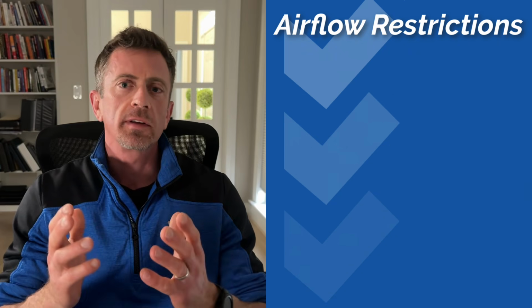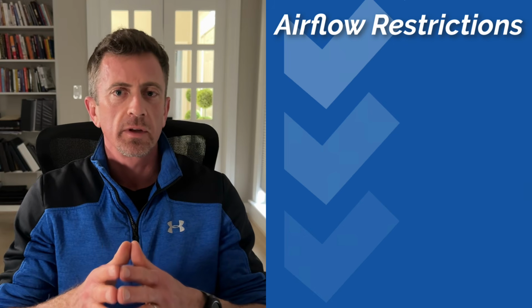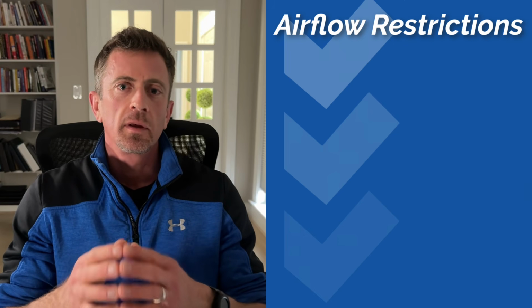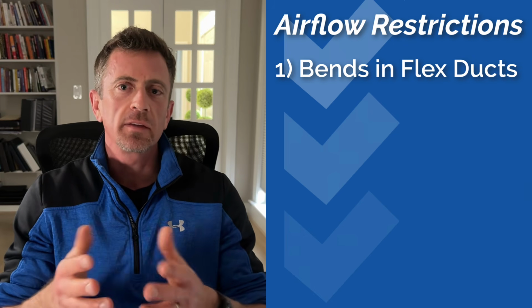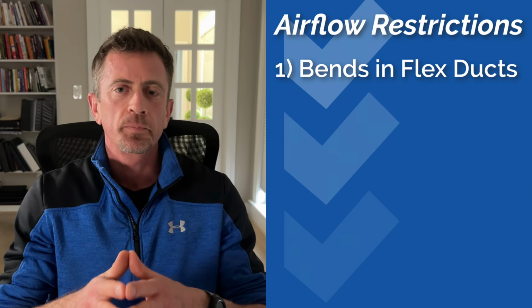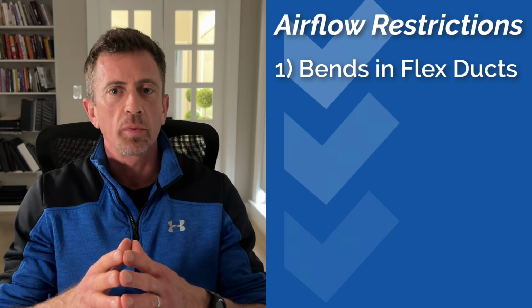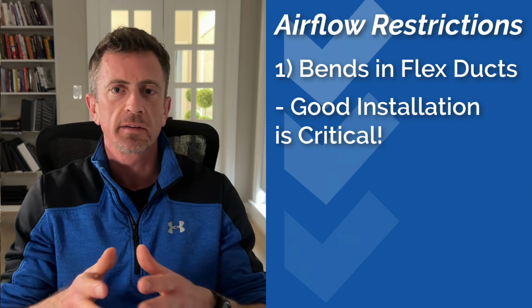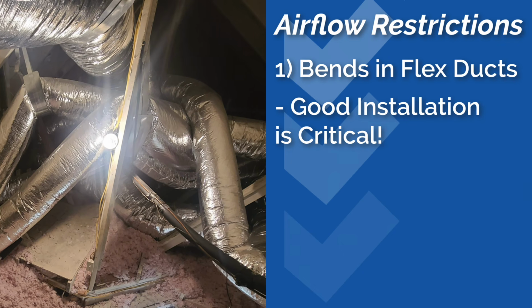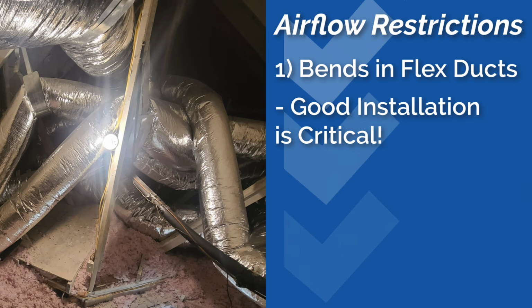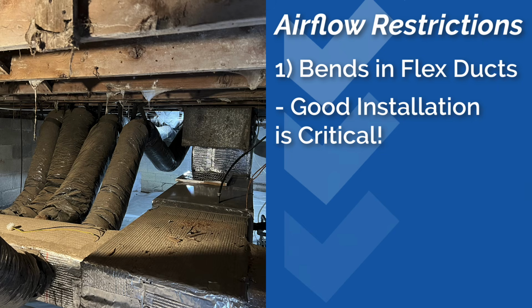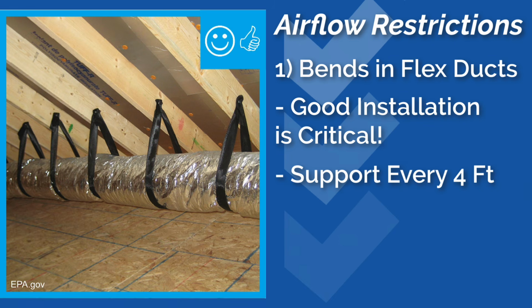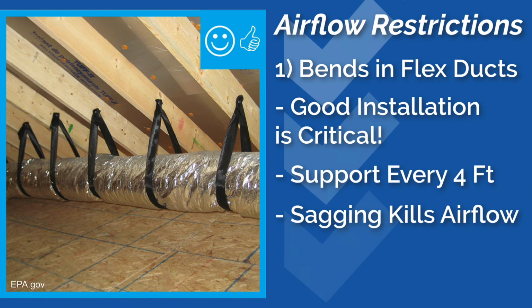The next section is on common airflow restrictions, and these are the bad guys. The first restriction up are kinks and bends in flex ducts. All ductwork needs to be installed properly, but especially flex ducts. Any sharp bends or kinks in them are going to restrict airflow. Another big thing here is that flex ducts need to be supported every 4 feet or so to prevent sagging, which can also kill airflow.